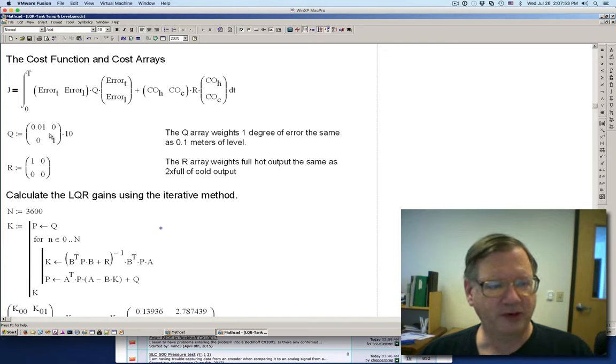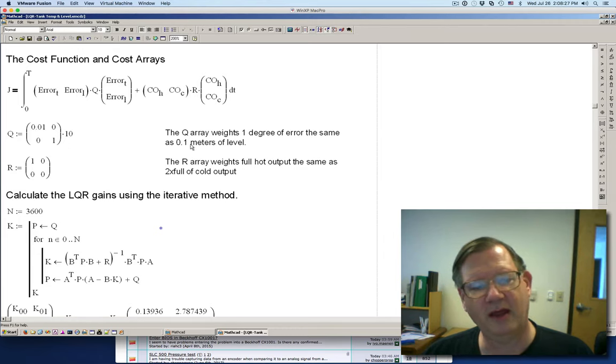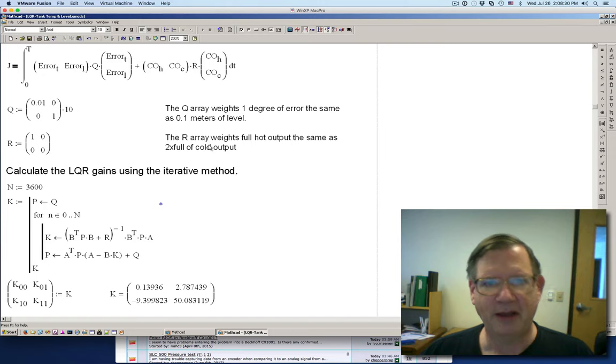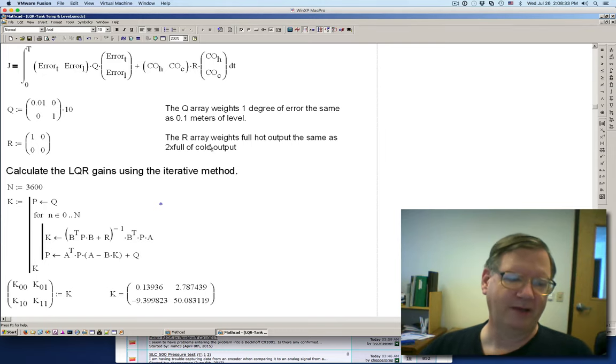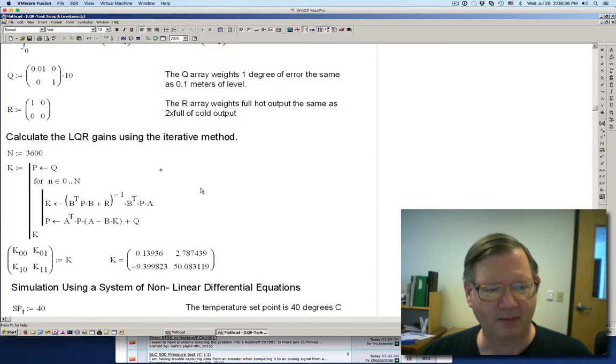And because this is the temperature up here and this is the level, I've got this weighted so that one degree of temperature error is the same as 0.1 meters of level. And the way that you calculate this out is you have to take the ratio of those two values, which is 0.1 over 1 and then square it. So then what happens is I have a 1 and a 0.01 up here. So that makes it so that one degree of temperature is going to be equal to one tenth of a meter of level. Now it's going to try to hold that, but it won't hold it exactly because of the different interactions.